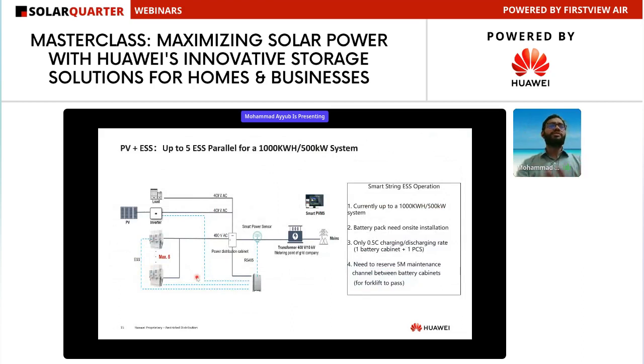Let's see how these systems work and how many we can connect in parallel. This is a solar system with a solar module, solar inverter, and the energy storage cabinet, which is our C&I product. We can connect a maximum of 5 in parallel, giving up to 1000 kilowatt hour, or 1 megawatt hour, and up to 500 kilowatt of capacity. This is modular, so we can have 200 kilowatt hour or 100 kilowatt, but if we need more power or energy backup, we can add more systems in parallel, up to a maximum of 5, reaching 1 megawatt hour. If you need more than that, we have another product, our utility product, which starts from 1 megawatt hour.